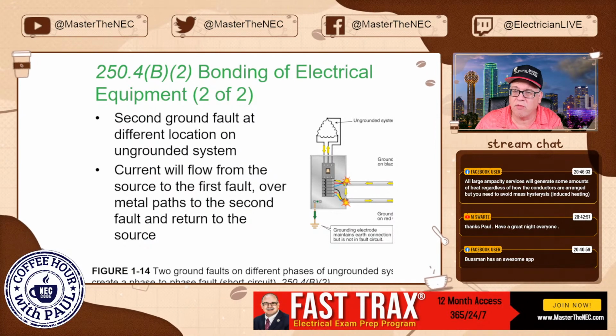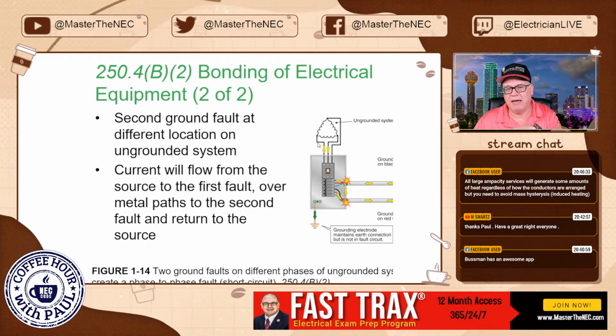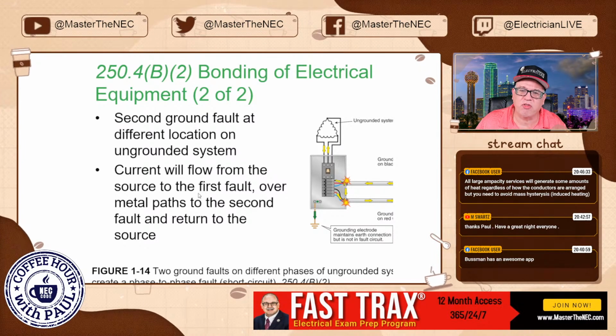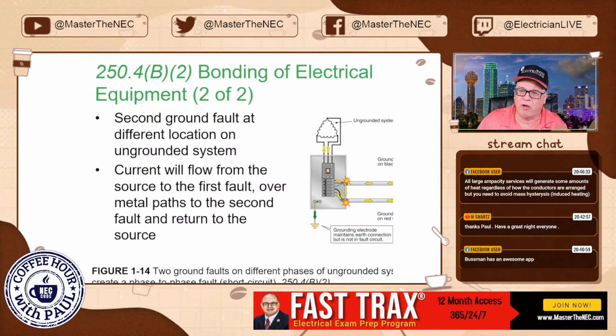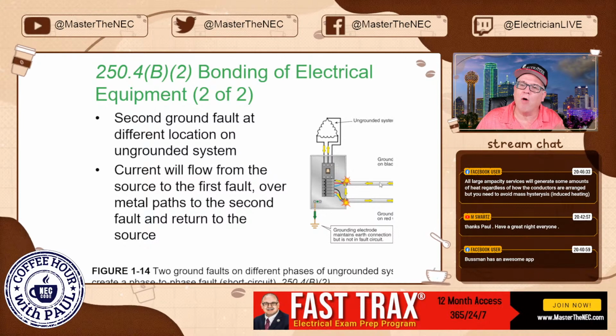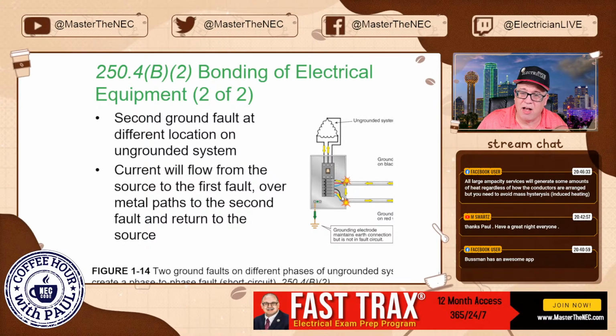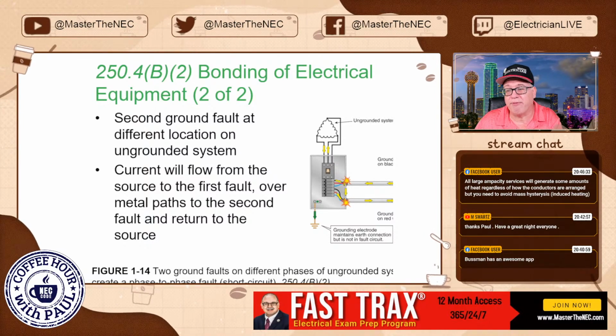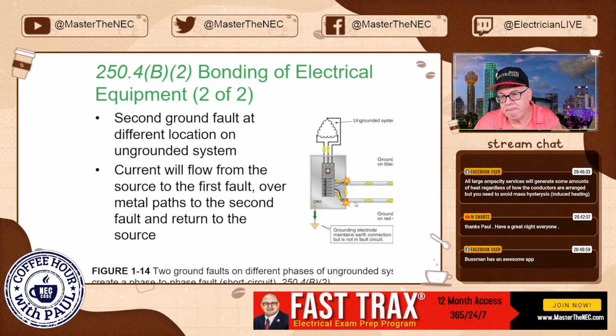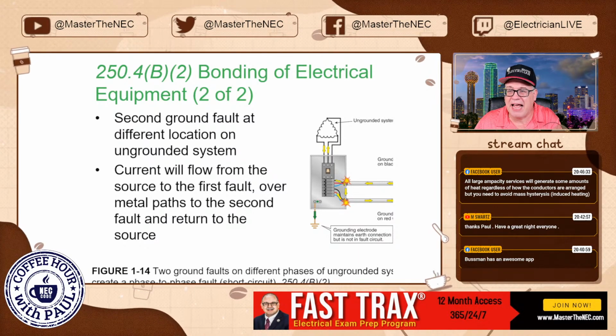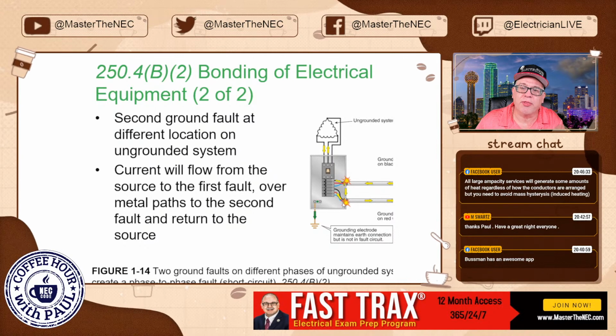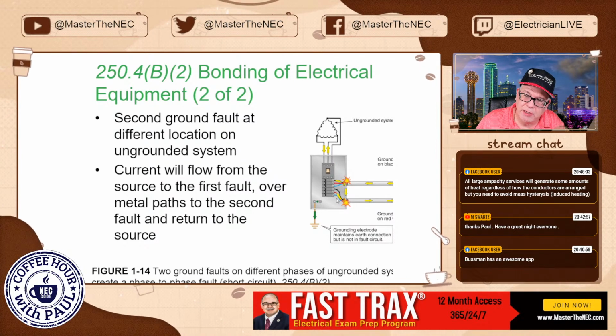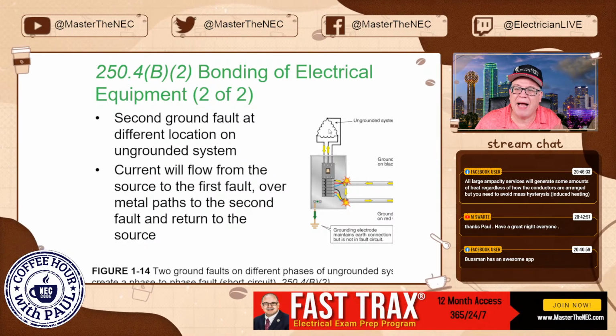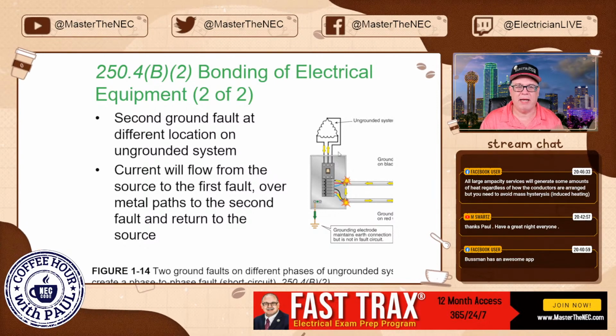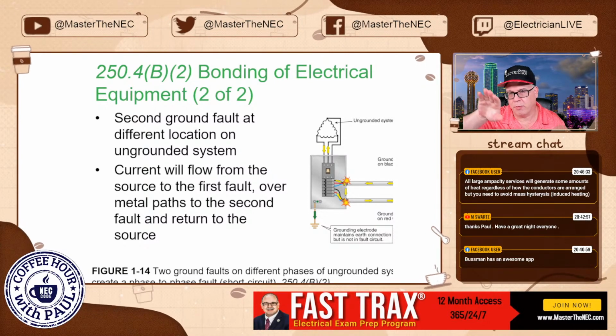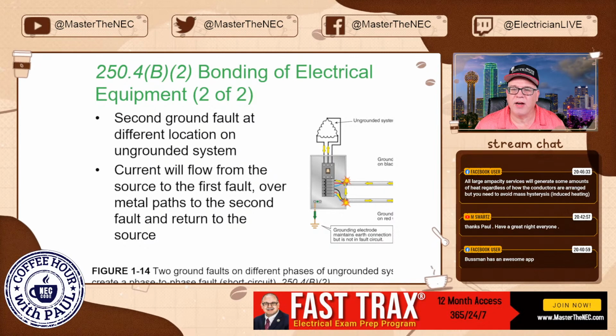Okay, so now you've got fault current coming in, right? So current will flow from the source of the first fault. So this fault here comes back through, over this metal path, down through the second fault path, okay? And then by doing that, it'll end up coming back through the red conductor, back over, and then go back, completing the circuit, and then guess what happens? Clear the breaker.